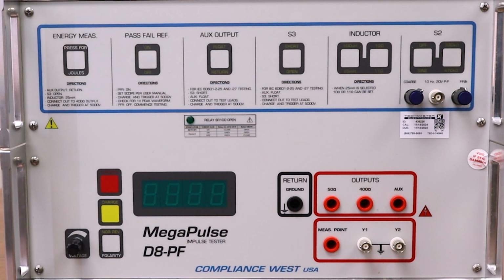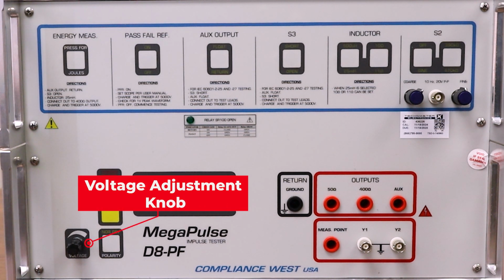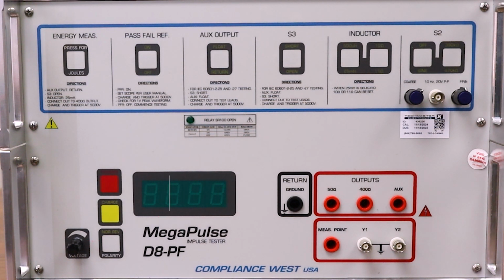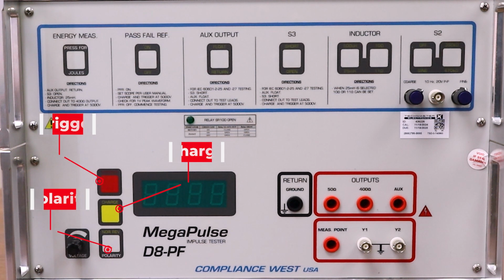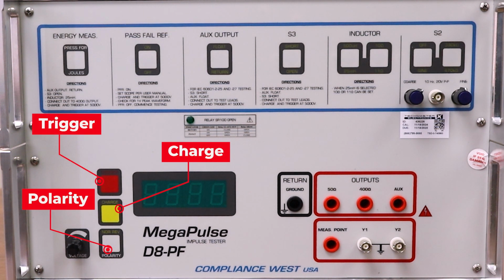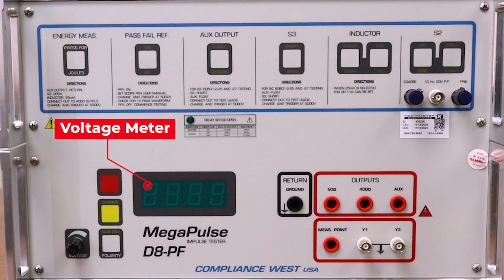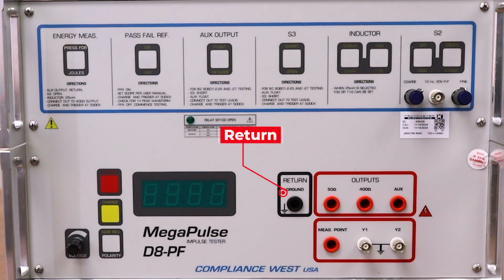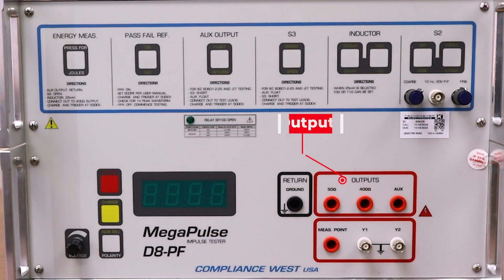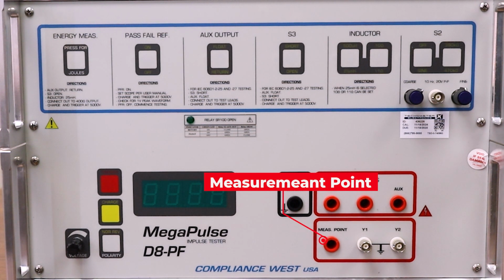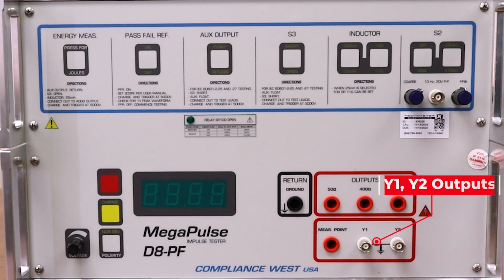Looking at the bottom section of the unit now, starting on the left in the corner, we have the voltage adjustment knob. To the right of that, we have the trigger, charge, and polarity buttons. Next to that, we have the voltage meter. On the right side of the unit, we have the return jack, outputs, and then below that, the measurement point and the Y1, Y2 outputs.